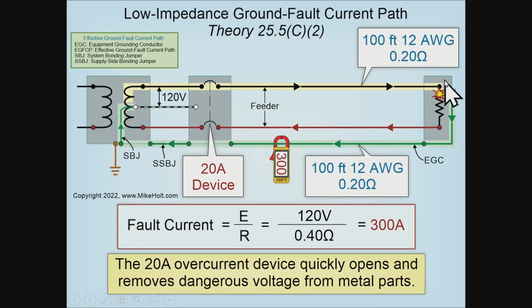So now let's look at the graphic here. So the code works this way. You have a transformer, a simple basic transformer. Electrons leave the source, go through a protective device. That's protecting against short circuit, ground fault, and overload. And there's a ground fault. Fault current travels on a wire that's called the equipment grounding conductor. Just know that it's a wire going back over to the source, right? So all these little components come together. Electrons leave the source. There's a ground fault. Ground fault current does not go to ground. It returns back to the source.